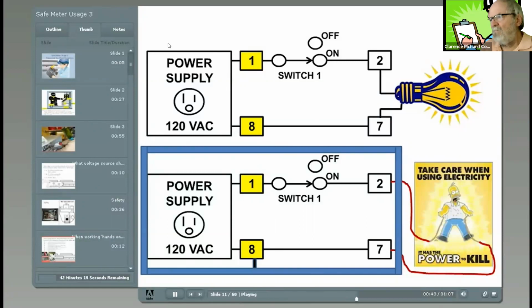If he completes the circuit by just merely touching the enclosure door, the high pressure on his right hand will seek the low pressure on his left hand, and Homer could be a dead man. Standing in shoes with wet boots on wet ground while touching the power supply terminals could also kill you. Wear PPE when possible. Ground one lead of the voltmeter with a clip lead and probe with one hand. If only one limb comes in contact with voltage, the chances of injury are minimized to slim or none.